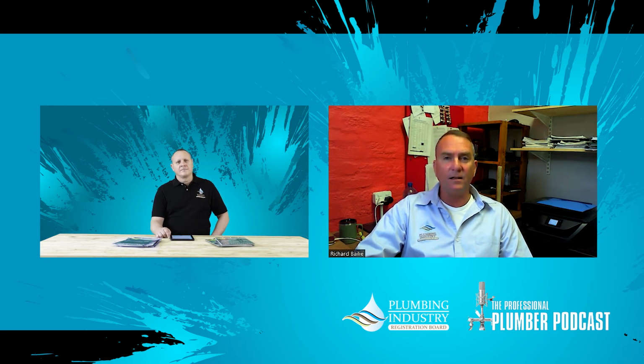But I can leave you with this thought: if you have a heat pump installed, perhaps it's a brand new home with a heat pump system, and you are experiencing that phenomenon whereby you initially get hot water out of your geyser and very quickly it drops down to lukewarm, or at least a cooler temperature, you more than likely are experiencing what we term disruption of stratification layers.